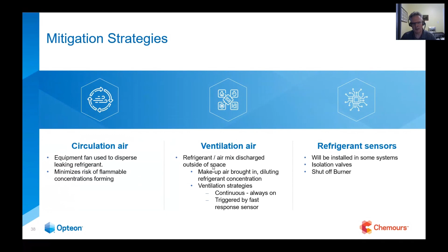When we look at walk-in coolers, someone is going to have to start doing the calculation of how big is the refrigerant charge, how big is the walk-in cooler area, and if this were to leak in that room, would it get within 25% of the lower flammable limit? So we may see things in walk-in coolers like refrigerant sensors that shut off that evaporator coil in that unit. We may see things like ventilation air into that space. We may see things like circulation air. So it's really dependent on the solution. It's going to be a little bit different when we first see this, but you're going to see more guidance on this from the manufacturers and more training. And I know HRAI, again, my shout out to them, I know they've put together a training program as well in handling A2Ls.